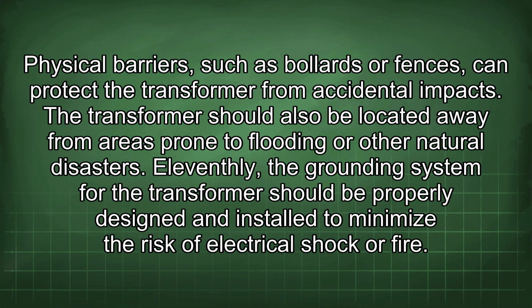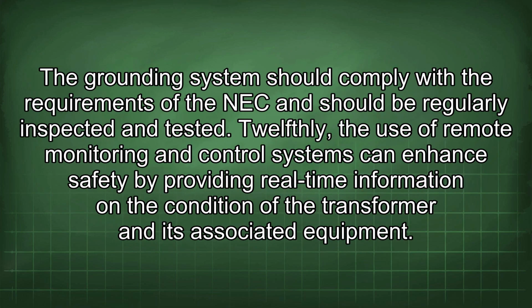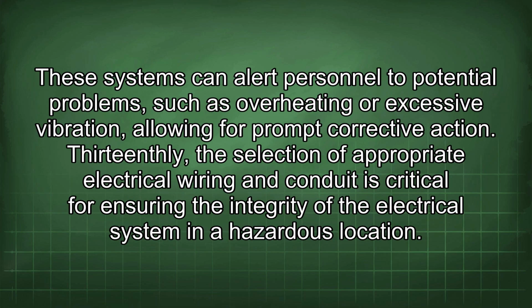11thly, the grounding system for the transformer should be properly designed and installed to minimize the risk of electrical shock or fire. The grounding system should comply with the requirements of the NEC and should be regularly inspected and tested. 12thly, the use of remote monitoring and control systems can enhance safety by providing real-time information on the condition of the transformer and its associated equipment. These systems can alert personnel to potential problems, such as overheating or excessive vibration, allowing for prompt corrective action.